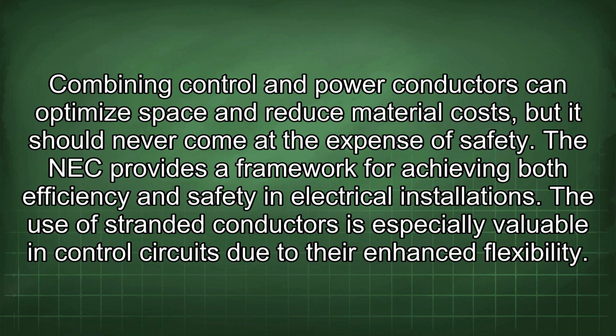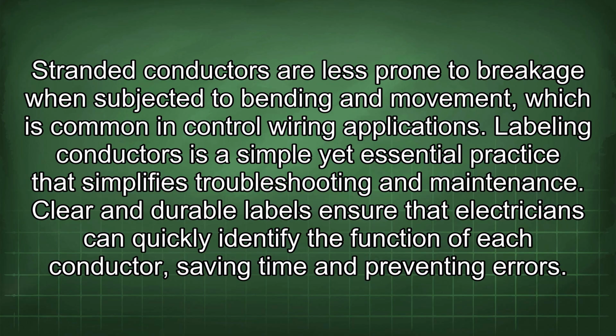Combining control and power conductors can optimize space and reduce material costs, but it should never come at the expense of safety. The NEC provides a framework for achieving both efficiency and safety in electrical installations. The use of stranded conductors is especially valuable in control circuits due to their enhanced flexibility. Stranded conductors are less prone to breakage when subjected to bending and movement, which is common in control wiring applications.